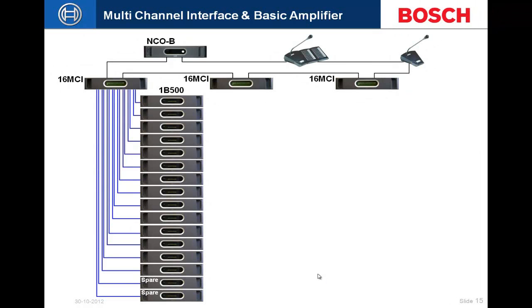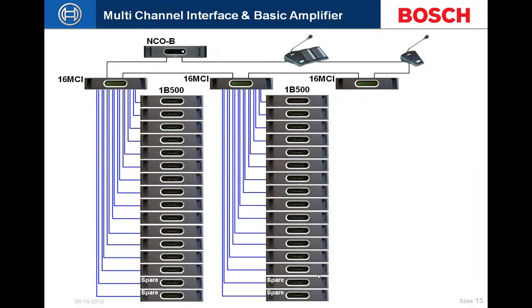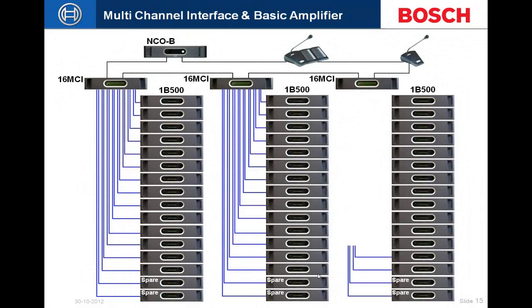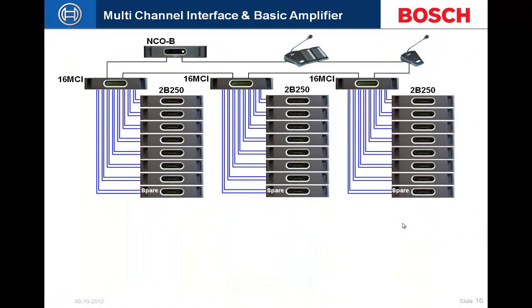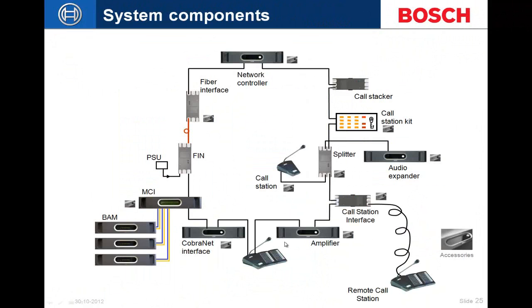Built-in supervision for basic amplifiers includes temperature sensing, output overload sensing, short circuit detection, ground short detection, and mains and backup power supervision. The front panel has LED displays for main and backup power status and VU meters for amplifier outputs. On the back, local audio inputs have volume controls and are automatically routed as a low-priority input directly to the amplifier's output. A higher-priority page coming through the MCI port automatically disables and overrides the local audio input.